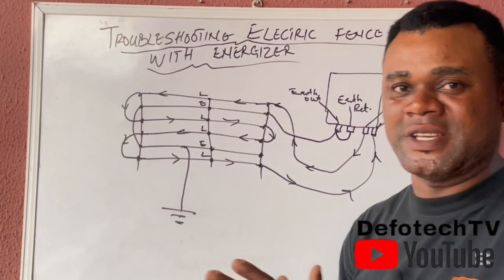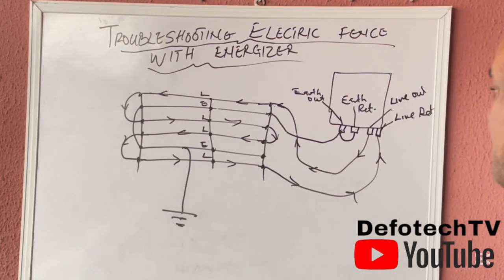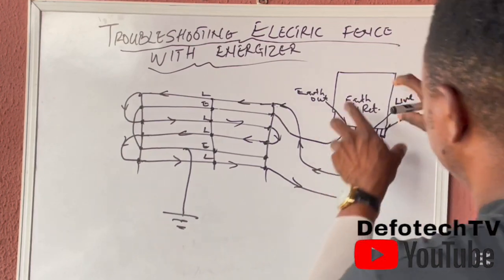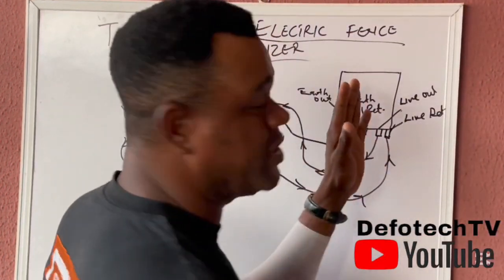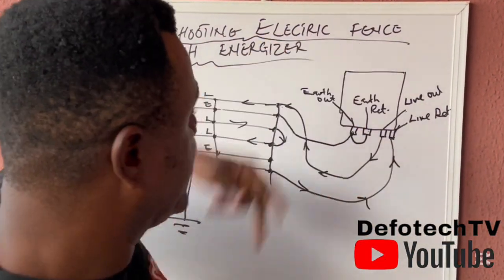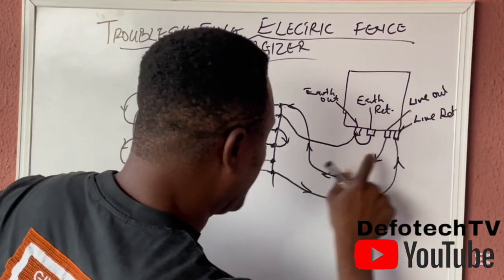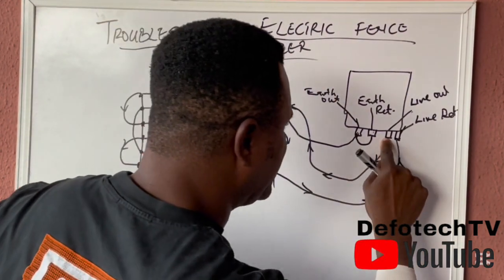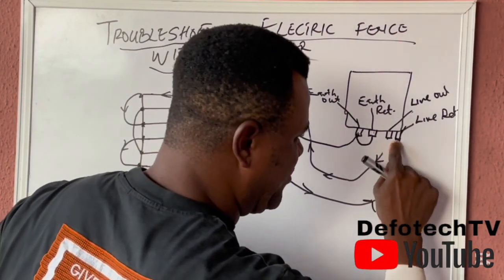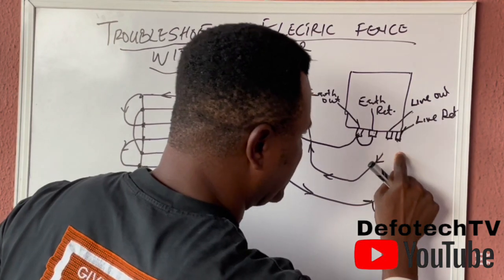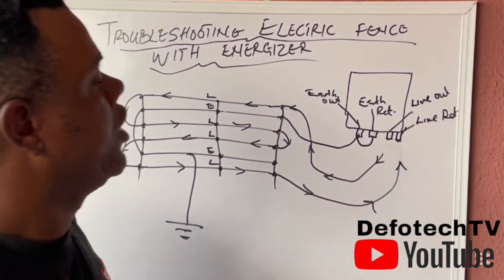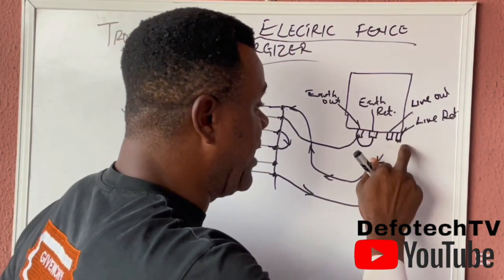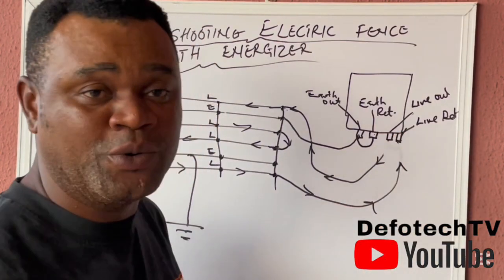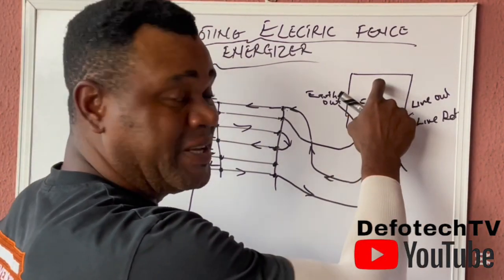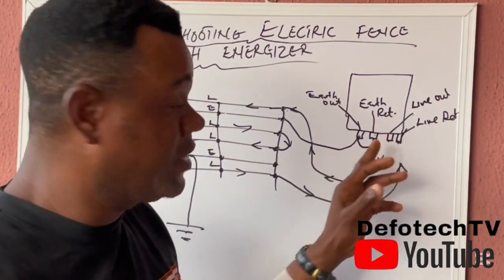So how do you test this, how do you check for the problem? All you need to do first is come to the energizer. When you get there, disconnect the cables going to the live and return terminals totally from the energizer. Now the live out and live return are left fallow. Make sure the energizer is turned off before you disconnect this.